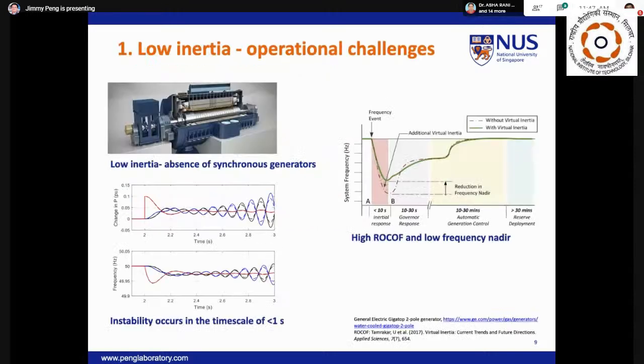So referring to the fundamentals of electromechanical dynamics, the machine's inertia helps to dampen the disturbances by reducing the magnitude of variation in the system frequency right after a fault or disturbance. In a utility grid, the time frame of electromechanical response is usually in the range of a few seconds. However, the adoption of inverter-based generators or low-rating diesel generators means the buffer zone of inertia will usually be less than a second. As we can see in these plots, the lack of inertia in a power electronic dominant grid can spiral to instability in a more violent manner. In literature, many research papers have reported ways to improve the frequency nadir during a disturbance through mechanisms like virtual inertia.